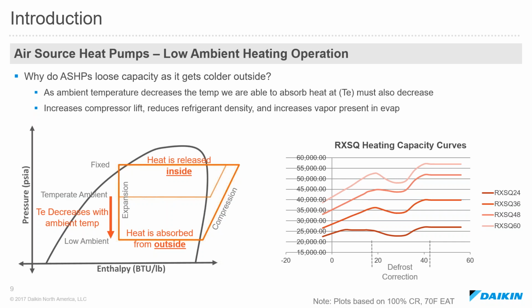So really, it's not going to be too significant until around 20 degrees outside, and it's going to depend on a lot of factors. This just represents a fixed set of conditions, just giving you an idea of what that looks like. But the general sense is around 20 degrees, you see a more significant drop in the capacity. And you do see a downward hump between 20 and 40 degrees. That's when defrost is a factor, when there's enough moisture in the air where frost builds up on our coil, and we have to go through this defrost cycle to melt that off, so we're not impacting our ability to exchange heat on that outdoor unit.